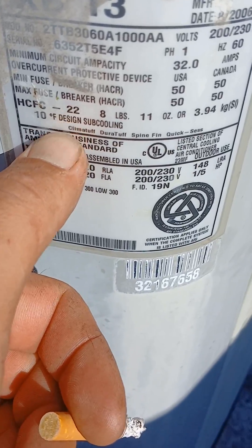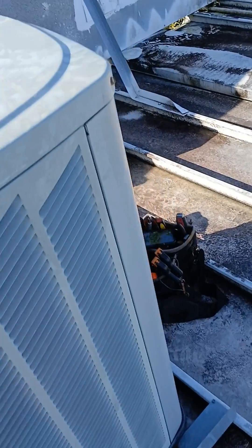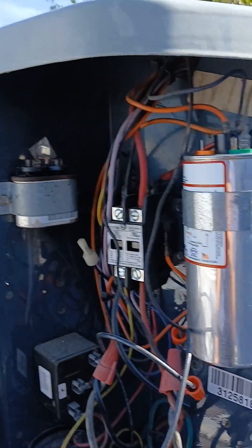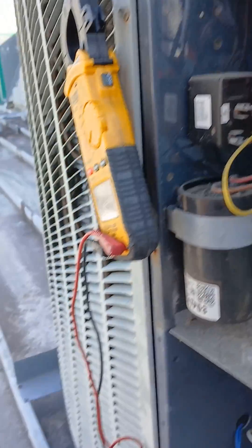So this is the old R-22 system. They had a jumper going over to the fan capacitor, which was giving it a little bit too much kaboom. That's an 80 µF.